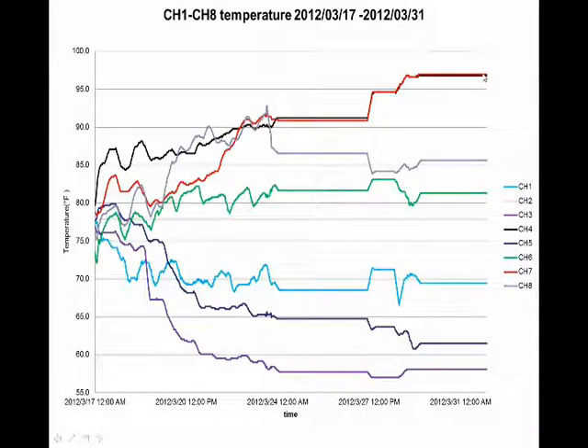Channels 7 and 8, as you can see, got up to 97 degrees F. It is not an alarming situation at all, because our concern is mainly that the mica is temperature rated to 150. We would not advise running the generator at a temperature of 100 degrees C, not F. I mean, 100 degrees C will become 212 Fahrenheit. So this is comfortable. The only thing that is curious is the spread of temperature. You can see channel 3 has a low of less than 60 degrees, about 57, 58.